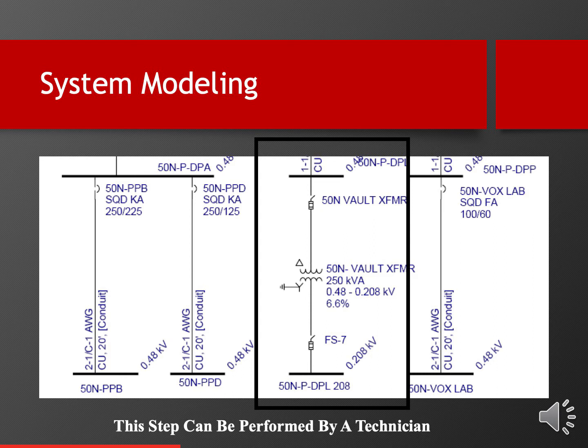Now, I mentioned at the bottom of this slide that this part of the process can be done by a technician. It does not need to be an electrical engineer to do this. In fact, we've had excellent luck using electricians to gather data. Once we got them teed up with the forms and things they need to gather and capture the information we need, electricians have done an excellent job gathering data. In fact, they know the system much better than the engineers usually. And as such, this is something that they can do. It lowers your cost of the study, and it's also probably even better than using engineers for that step. So for what it's worth, that can be done by a technician. Let's go to the next slide.